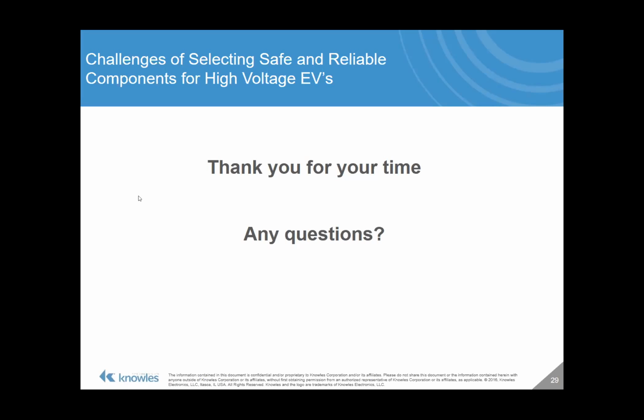When should I use an AC voltage DWV versus a DC test? I would answer that quite simply: when your specification tells you. We use a DC test as standard, but if the component has an AC rating, then we would consider it necessary to do an AC test, at least on a sample basis as well. But ultimately, it comes down to specification. What is your final requirement?